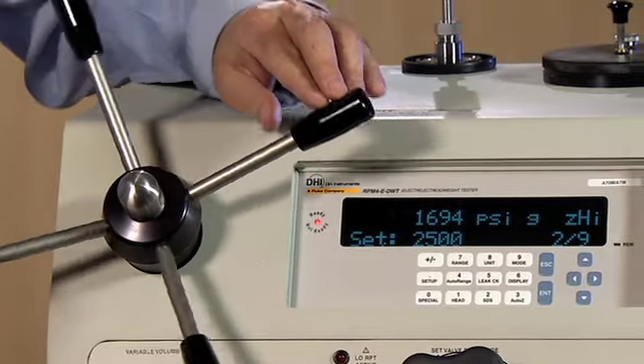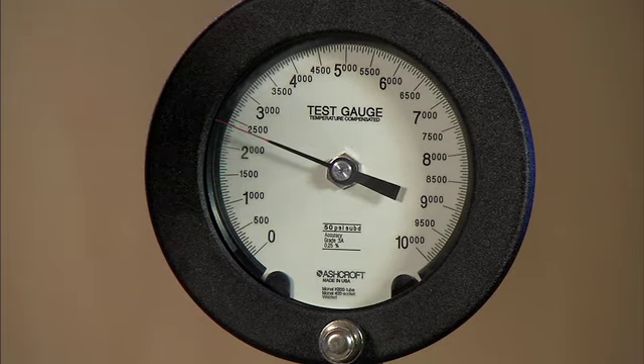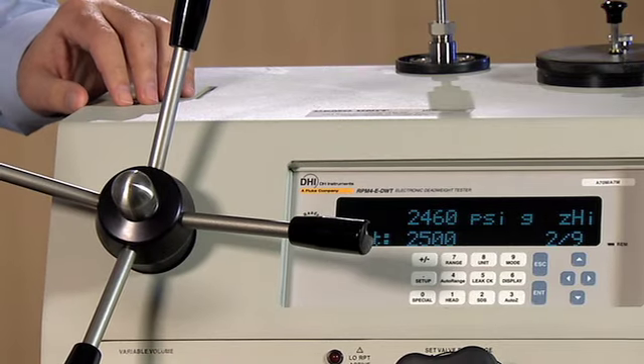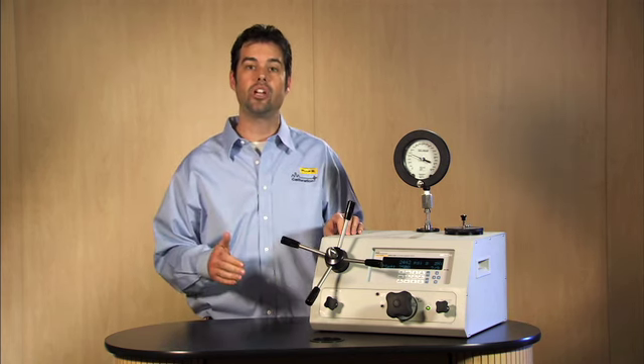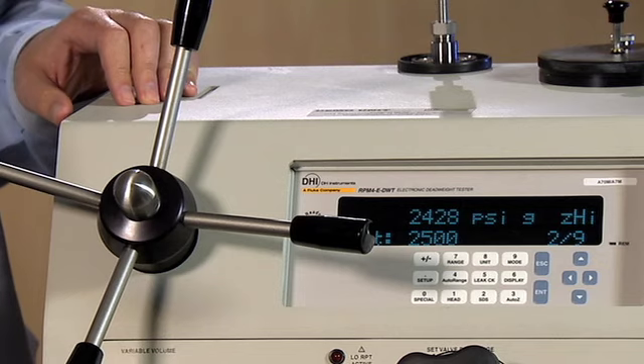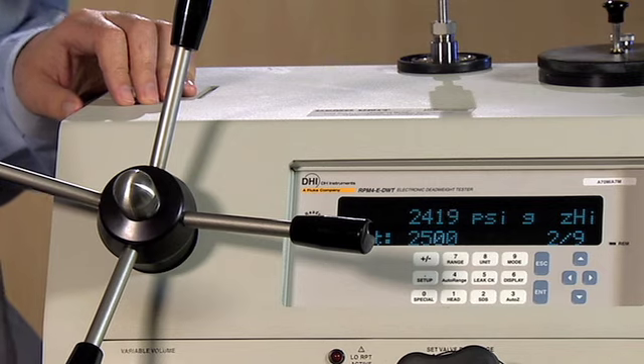So let's go ahead and use the variable volume to get up to 2,500 psi. We're near 2,500 psi. Now typically in a gauge calibration you want to get to a cardinal point, so we're going to use the variable volume to get right to that 2,500 psi.